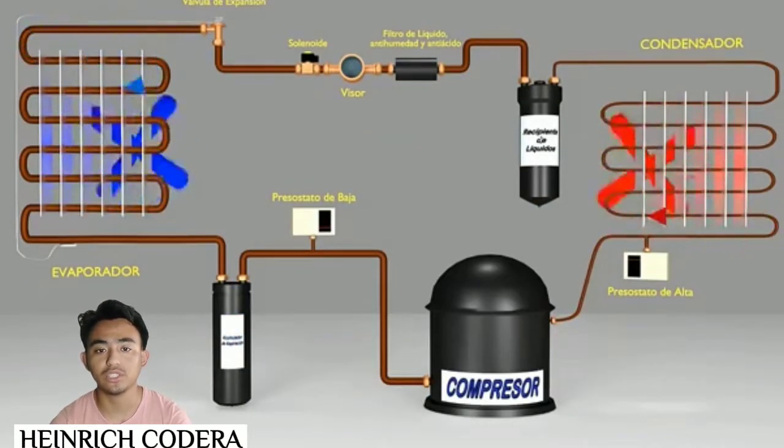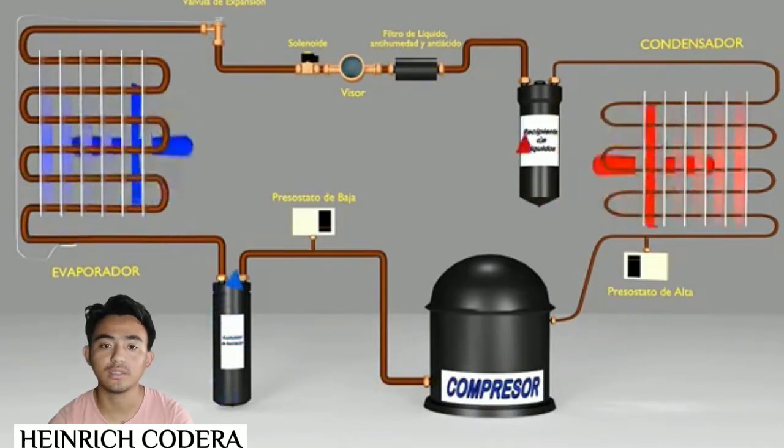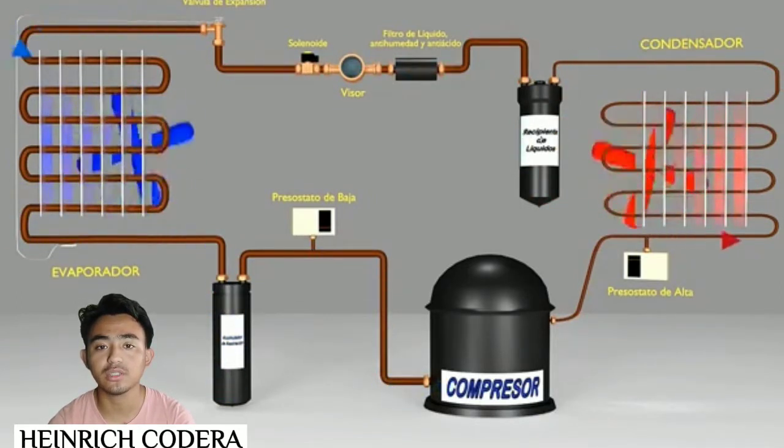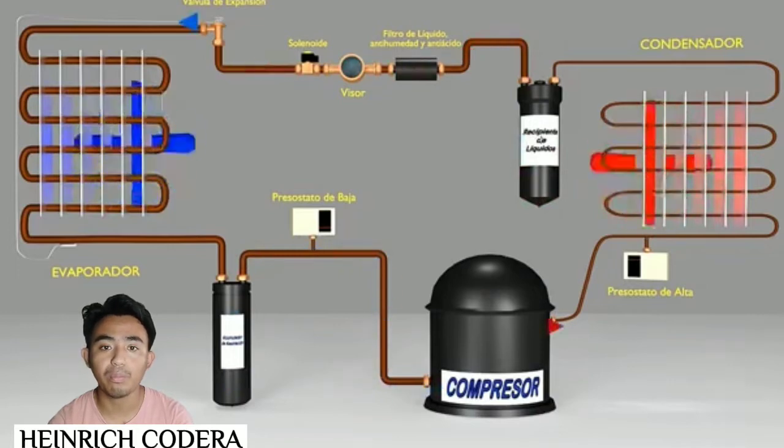Improper operating conditions as well as pollutants inside the loop might cause the expansion valve to decay and malfunction, because it operates at high pressure and is temperature sensitive. The AC system will not cool adequately if the expansion valve is jammed open or clogged.